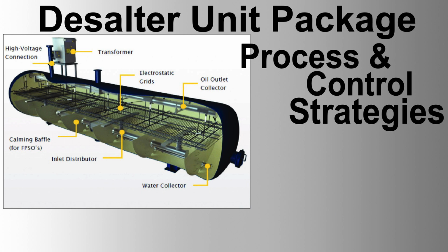Shutdown loops. 1. High-level shutdown. If the water level in the desalter exceeds a predetermined limit, the level transmitter LT101 triggers a high-level shutdown, closing the crude oil inlet valve PV301 and stopping the water injection. 2. High-pressure shutdown. If the pressure inside the desalter exceeds a safe limit, the pressure transmitter PT301 triggers a high-pressure shutdown, closing the crude oil inlet valve PV301 and stopping the process.